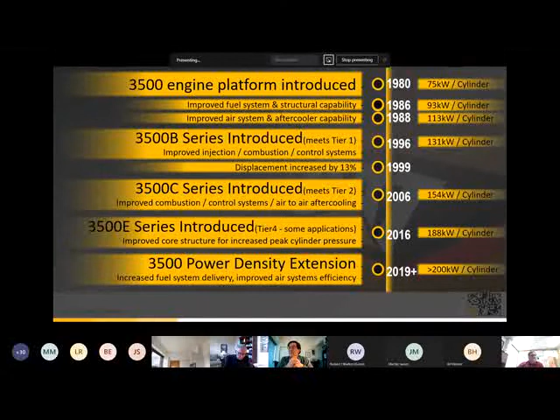The 3516E standby and mission critical gen sets are rated at 3 megawatts now. With that size of unit at 78 liters of displacement, they have a charged air cooler. We are able to meet the NFPA 110 spec for a 10-second start time for hospitals.